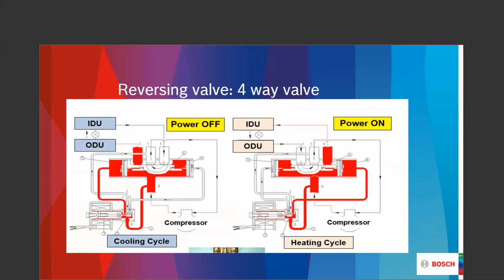And what we found out that particular week is that because my system is a B operated reversing valve, I can be an air conditioner if you just give me a Y call and a common. But we would like for you to energize the reversing valve, even in the summertime, to make sure that it fully opens and it fully closes, so that we have the true effect of the cooling capacity.